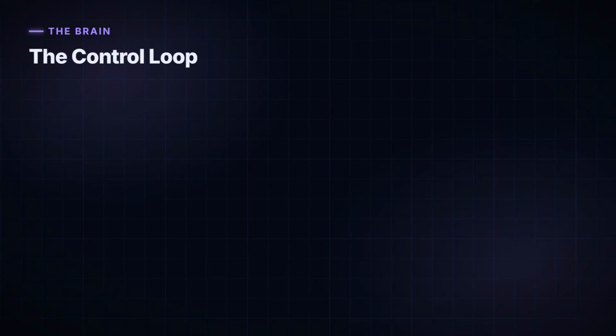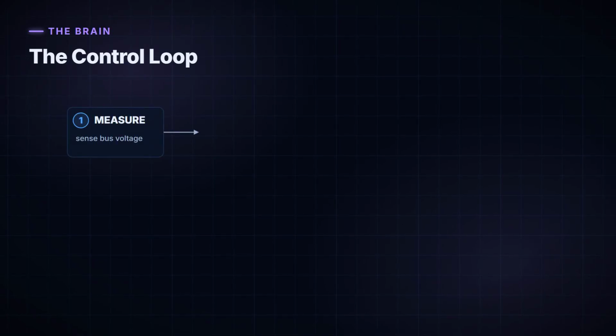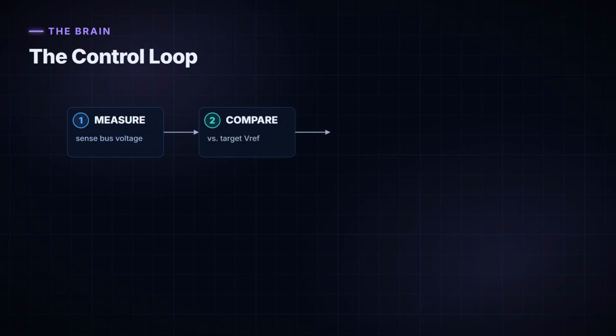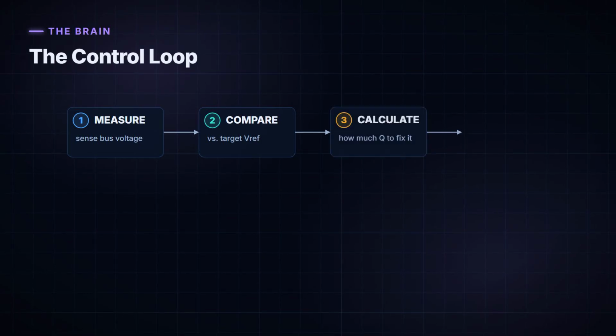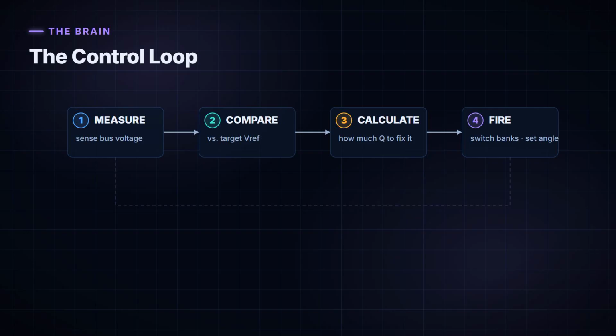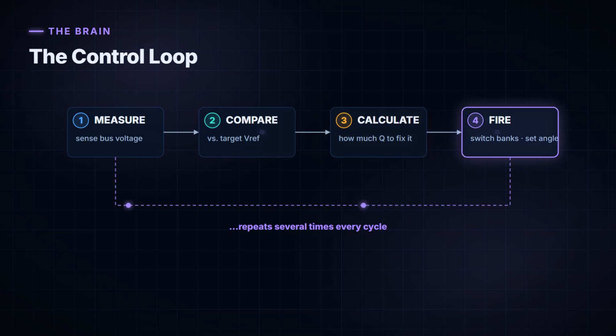None of this works without a brain making decisions hundreds of times a second. So let's look at the control loop. It's a beautifully simple idea, repeated continuously. Step 1. Measure the actual voltage at the bus. Step 2. Compare it to the target voltage we want. If there's a difference, an error, Step 3. Calculate exactly how much reactive power we need to cancel that error. And Step 4. Translate that into firing commands, which capacitor banks to switch in, and what firing angle to send the reactor. Then it loops, measuring again, correcting again, around and around, several times every cycle.